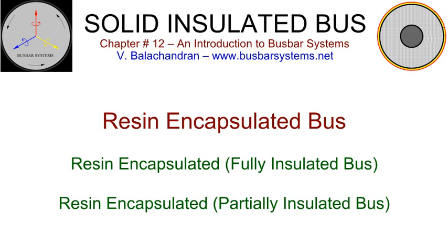The insulation also protects the conductor from experiencing a fault caused by accidental bridging of phases or phase and earth by birds and rodents in outdoor switchyards. Resin encapsulated bus are manufactured up to a length of 10 meters, 33 feet 4 inches, and a rating of 3,150 amperes with aluminium and 4,000 amperes with copper tubular conductors. The degree of protection provided for the conductor is IP67. The conductors are joined at the site with aluminium or copper laminates of compatible current rating with a cylindrical enclosure sleeve that offers a minimum degree of protection of IP54 for indoor and IP68 for outdoor installation.